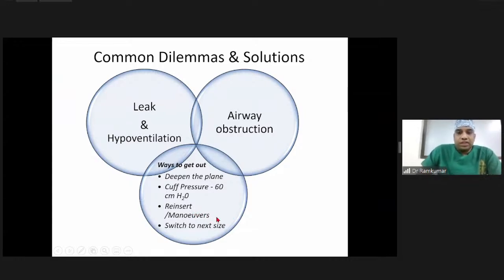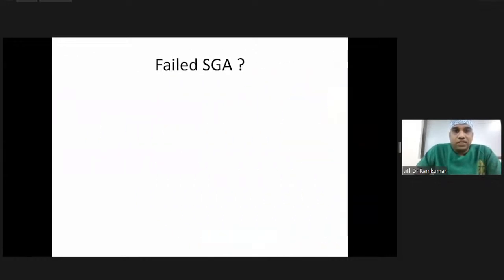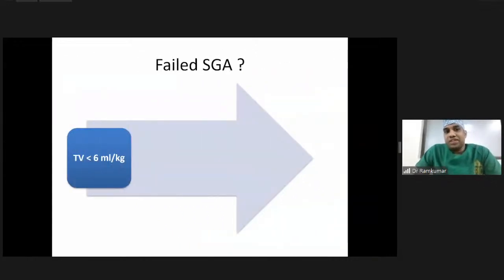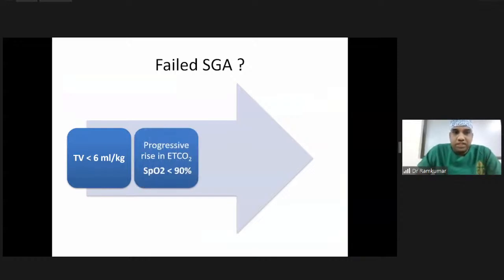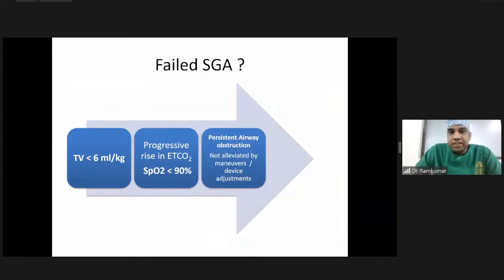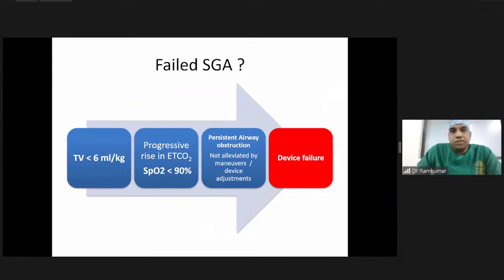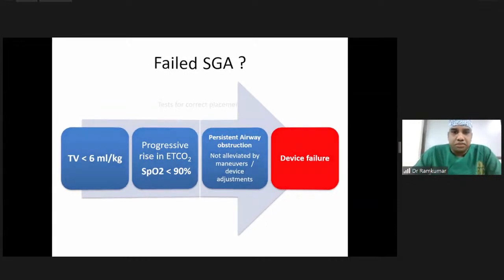And if nothing works at all, then you can call it a failed SGA. So what is the definition of a failed SGA? If you are not able to achieve a tidal volume of at least 6 ml per kg, that is persistent, and there's a progressive rise in EtCO2, and the SpO2 is less than 90%, and despite doing maneuvers and size adjustments there is persistent leak or upper airway obstruction, that means the device has failed. You have to switch over to the next best possible device or switch over to an endotracheal tube, depending upon the necessity of the surgery or a resuscitation.